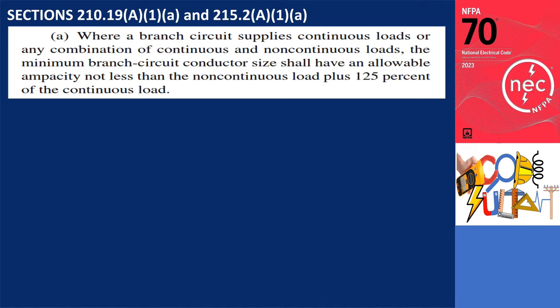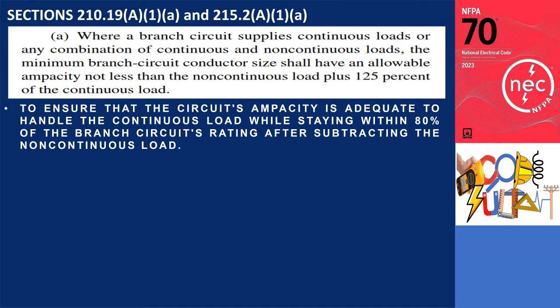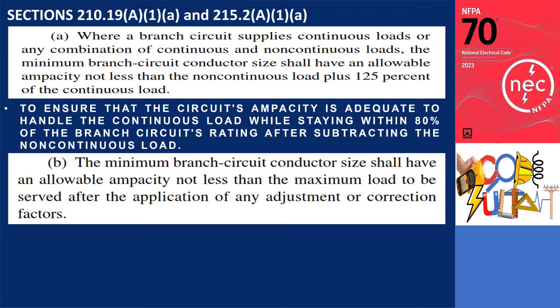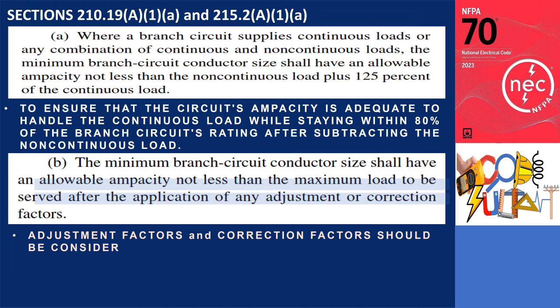Going back to Sections 210.19A1A and 215.2A1A, the intention behind this rule is to guarantee that the circuit's ampacity is adequate to handle the continuous load while staying within 80% of the branch circuit's rating after subtracting the non-continuous load. It is worth emphasizing that the rule also accounts for the interaction between the wire and its surroundings. Adjustment factors for ambient heat or mutual conductor heating should be considered when determining the resulting ampacity. However, the resulting ampacity must remain equal to or greater than the load, regardless of whether it is continuous or not.